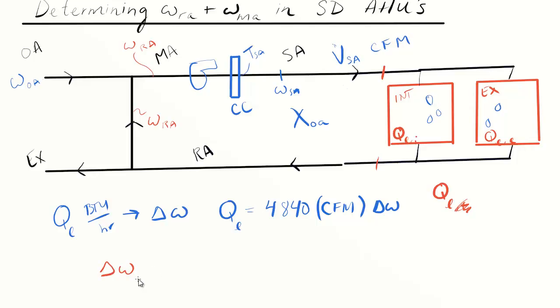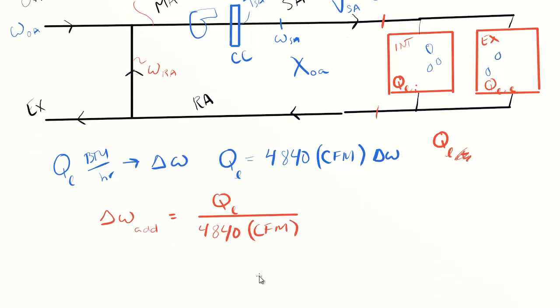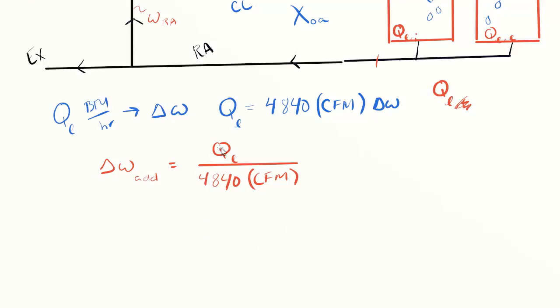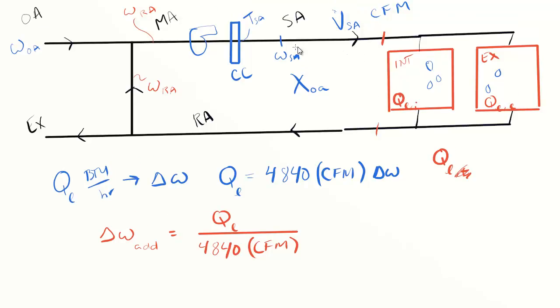If we want to know the delta difference in humidity ratio across from supply to return, that delta omega added is just the total latent load divided by our constant 4840 and the amount of dry air flow through the space. This is in BTU per hour and cubic feet per minute, the total CFM going through the single duct system.